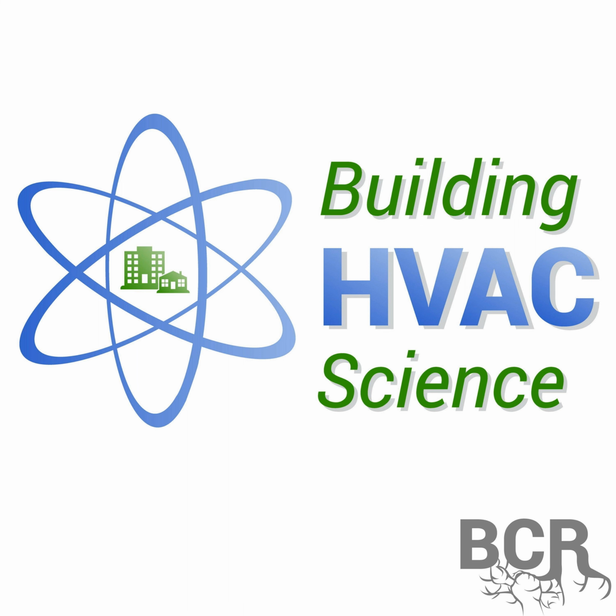So that's why a lot of HVACR pros use capture hoods. They're capturing the sneaky air. The sneaky air is often expensive air because the HVAC system has created this air with the correct temperature, humidity, airflow, delivered it to the correct location, etc. It serves no one to misplace or lose that air. Oh, and by the way, the air's density may also affect the way you measure air. I call this the Erzenberg uncertainty principle, pivoting off the Heisenberg uncertainty principle in physics. You can look that up in Wikipedia if you're really interested in that. These are some of the major factors combining to make airflow such a challenge to measure.